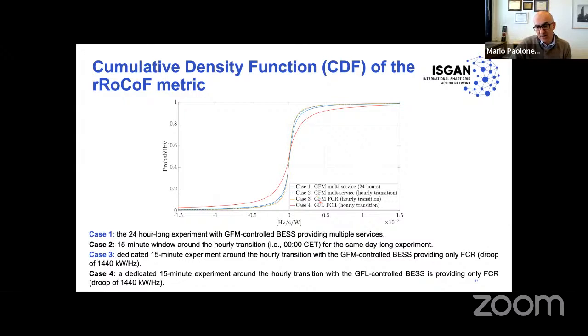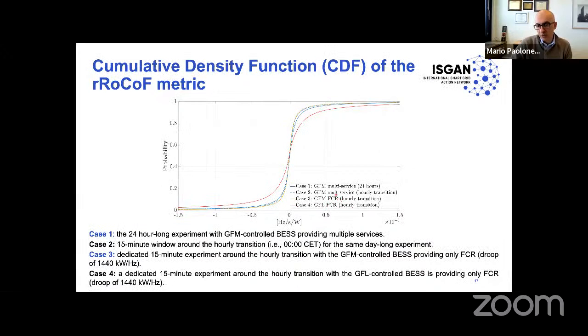And case 3 is the grid forming units providing only the primary frequency control, and not the multi-service. Why did we use case 3? Essentially because we wanted to be sure that the superposition of the dispatching was not disturbing the grid forming action with respect to the primary frequency control. And the reply was positive, because you can see that these 3 curves are basically superposed. So what you can say is that the multi-service provision or the single provision of frequency control reserve are essentially decoupled from the frequency dynamics perspective with respect to this relative RoCoF.